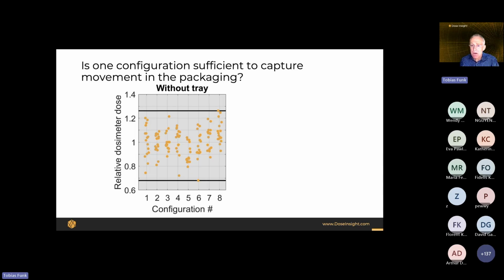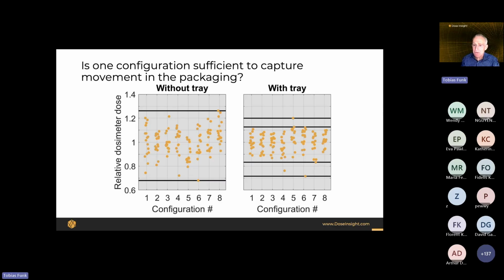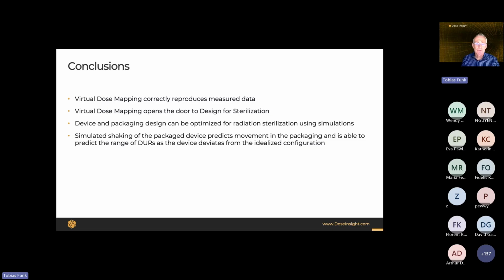And we can do the same for the configuration with a tray. And we see that it is much more confined than without the tray. But we also find that there are some outliers. So there are some cases where the dose range is actually significantly higher. So you see immediately the value of doing more than one configuration, because you need to address these outliers. And that would be the next step in the packaging design, to see how we can further constrain our device to make sure that we don't have these outliers. Well, with that, I want to conclude.